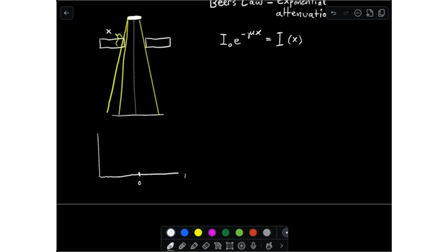So if this time we allow some of the beam to pass through these collimators and hit outside the edges of the field, the differential contribution from a point in the source will be further lowered, not only by the inverse square law, but also exponentially by the length of the sector over which it traverses the collimator. So what we're going to see is actually a very similar, continuous, smooth decline, but with additional contributions due to this previously unaccounted transmission.